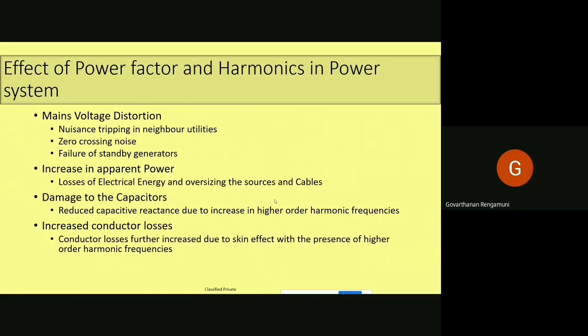Now, the effect of power factor and harmonics in the power system. This slide discusses the effects; it is a listing, and we can go one by one. The first one is mains voltage distortion. You are injecting current harmonics into the grid. These current harmonics cause a voltage drop across the grid impedance, so your point of common coupling is getting polluted. At the same point of common coupling, other utilities are also connected. They are called neighbor utilities.